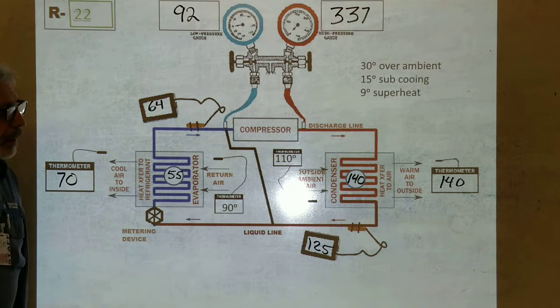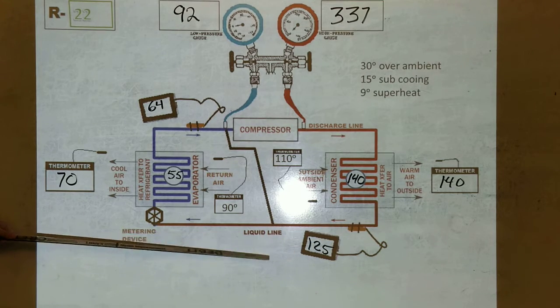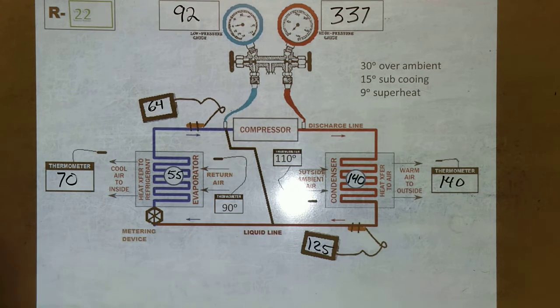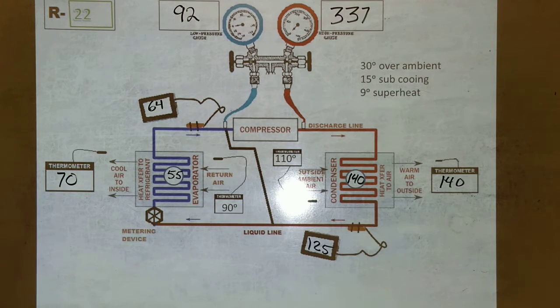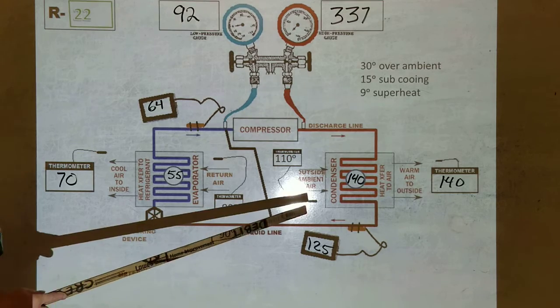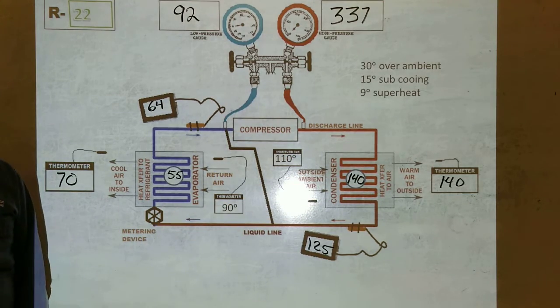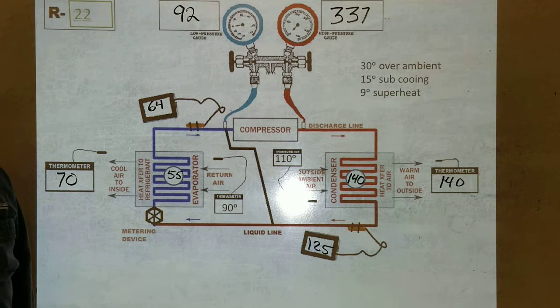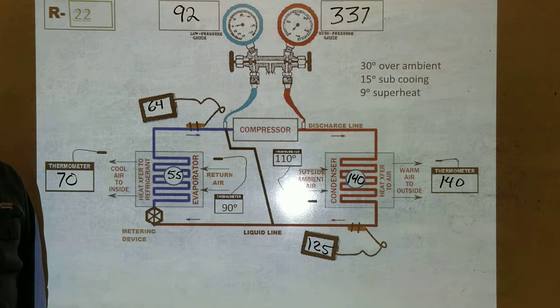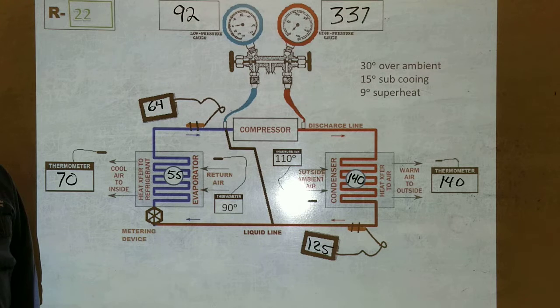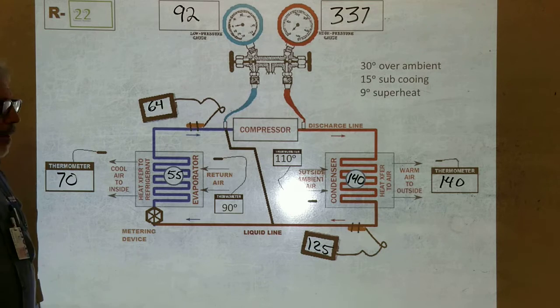And the same thing on the subcooling, we wanna ensure what goes in this line? Liquid. That's why they call it a liquid line. Yeah, okay. So 140 degrees, what's happening with the refrigerant at 140 degrees here? Evaporating. What is it? What's happening? No, it's not evaporating. What does it do in a condenser? Condensing. Okay, does that mean evaporating? No, it's condensing. It means condensing.